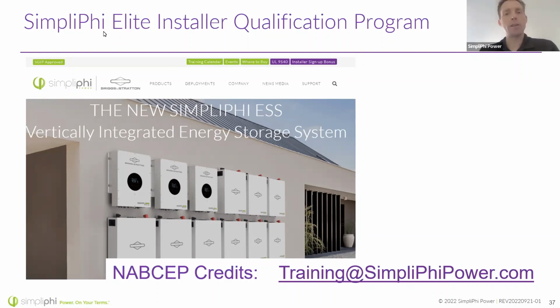Kurt, it would be a little easier on the battery to limit the current rating to 80% of capacity, but the C/2 discharge rate is fairly conservative. In fact, our batteries can charge and discharge at a rate of C for 10 minutes. The C/2 is really there to protect against the batteries discharging too fast and creating too much heat. So if you're not discharging for too long, there shouldn't really be an issue. You can do it. It might have a small impact on battery lifetime, but for the most part the C/2 should be just fine.